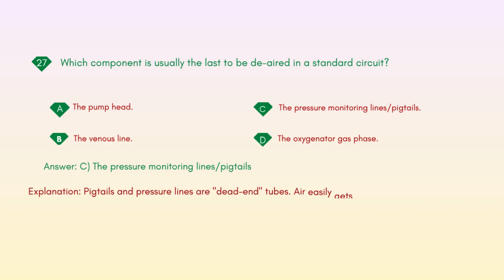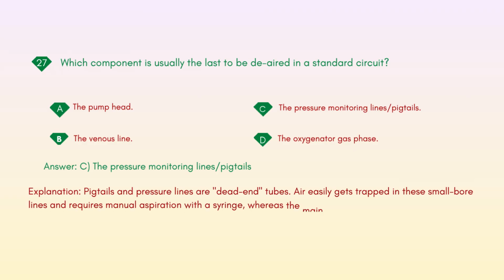Explanation: pigtails and pressure lines are dead-end tubes. Air easily gets trapped in these small bore lines and requires manual aspiration with a syringe, whereas the main circuit uses the bridge for bulk de-airing.